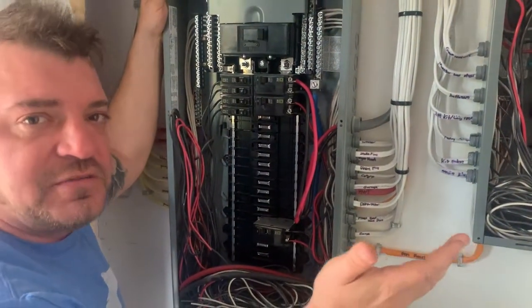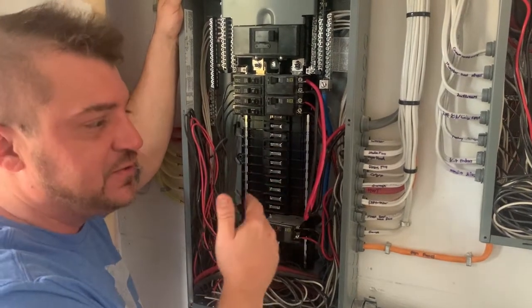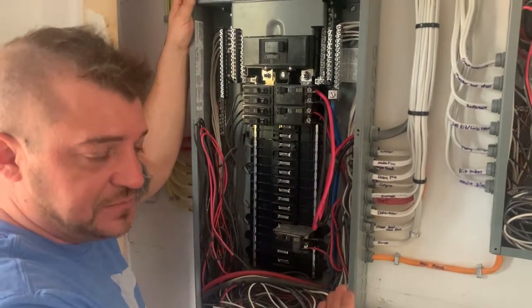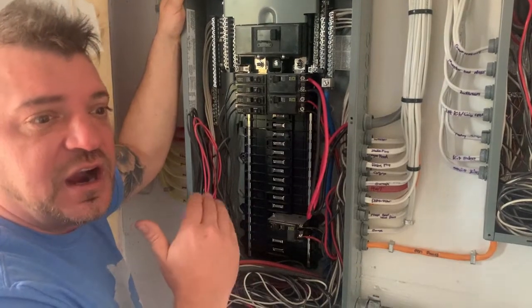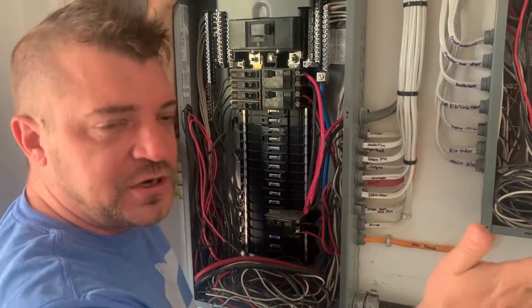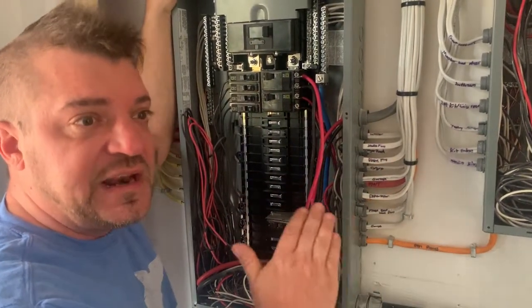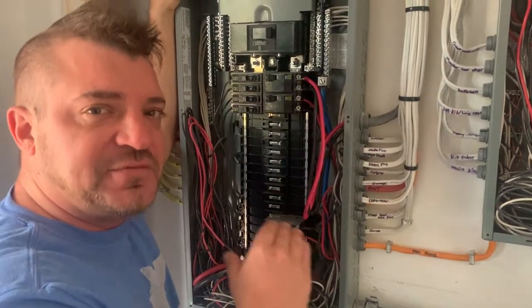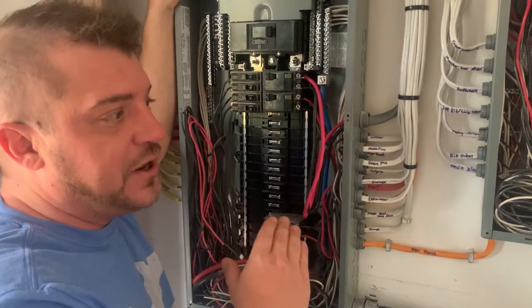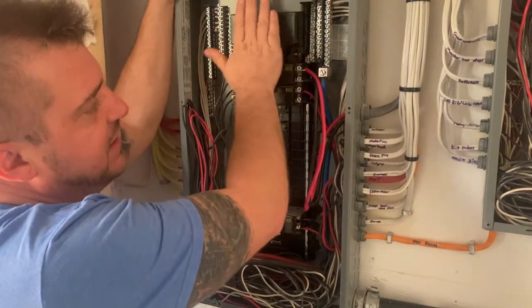For our final inspection, we actually need to run a megger test to make sure that the neutrals and bonds are separated from the panel onward, or the sub panel onward, so that we don't get any what we call grounded neutrals. If we get any of those in the house, we then have to correct them to meet code and properly pass.